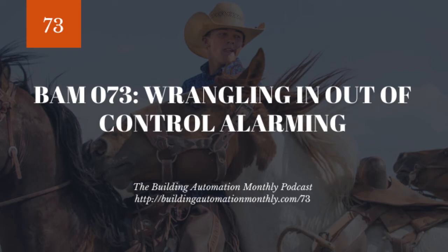You can just name everything VAV, AHU. But if you take that one more step and identify the floor it's on, or the building it's on, that makes such a huge difference. It's the same with alarming, and that one step is called alarm segmentation—this is where you set the priority level associated with your alarms.